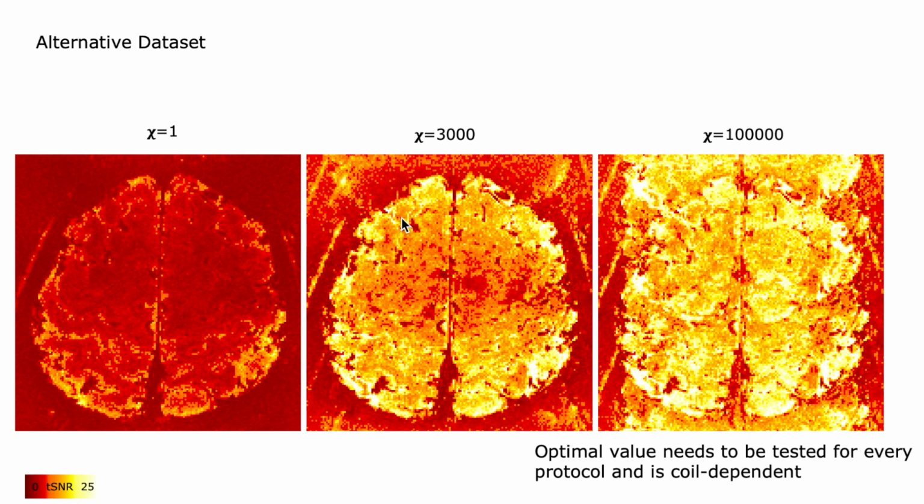And I think there is no reason why we shouldn't play with this parameter. There is no reason why the whole universe of MRI and acceleration should use the exact same grappa algorithm, because if you do liver imaging at 1.5 Tesla or layer-dependent fMRI at 7 Tesla, obviously you have a very different coil setup, a very different sensitivity to ghosting or B0 homogeneity. So it makes sense for every setup to also optimize this parameter, as you would with any other parameter like echo time or TR.